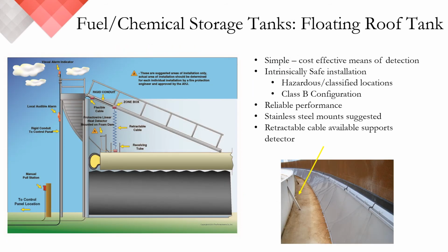In addition to fixed roofs, we also see a lot of floating roof tanks, as well as fixed floating roof tanks. In a floating roof tank, the roof forms a seal around the inner wall and will rise and lower with the level of the material it contains. The linear detection is installed in much the same way as a fixed roof, with a few exceptions. As you can see here, the detector is positioned just above the rim seal and around the perimeter of the floating roof.